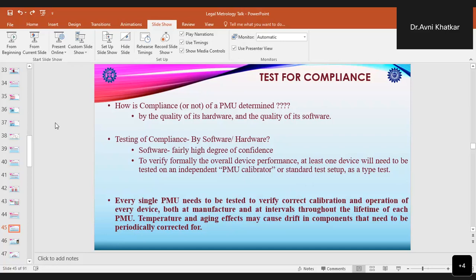Also, it may be seen that every single PMU needs to be tested in order to verify correct calibration and operation of each single device, both at the manufacturer end at the time of manufacturing, and at specific intervals throughout the lifetime of each PMU, because temperature and aging can also affect and cause drift in components that need to be periodically corrected for.